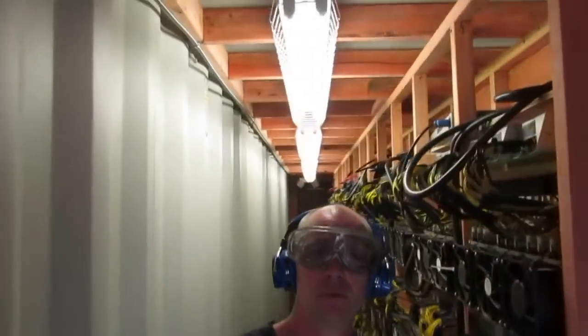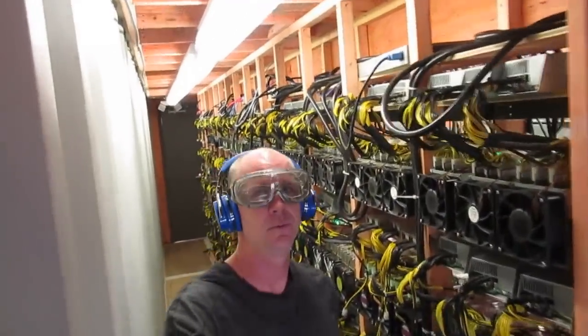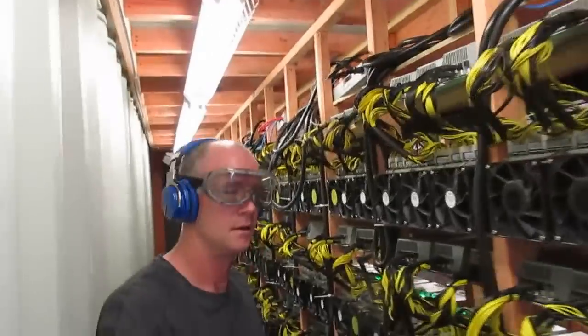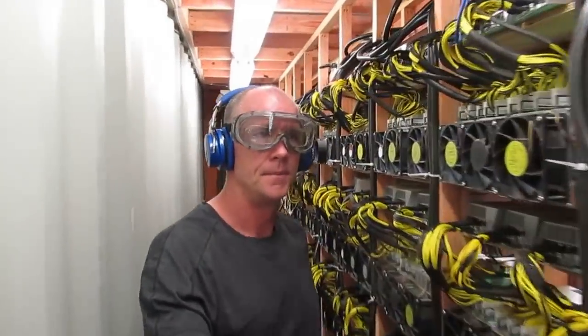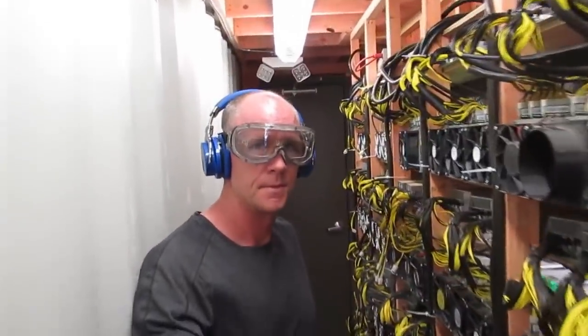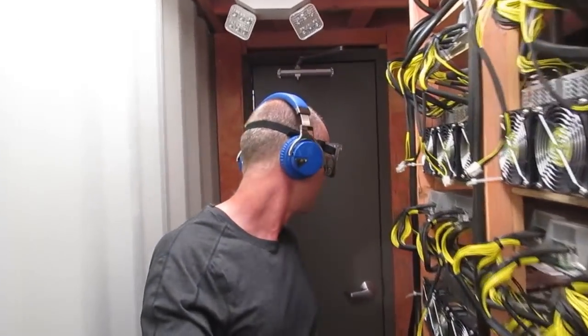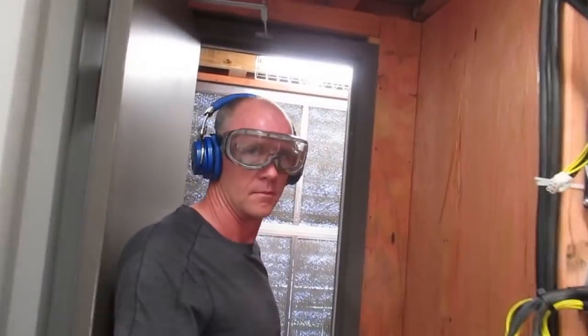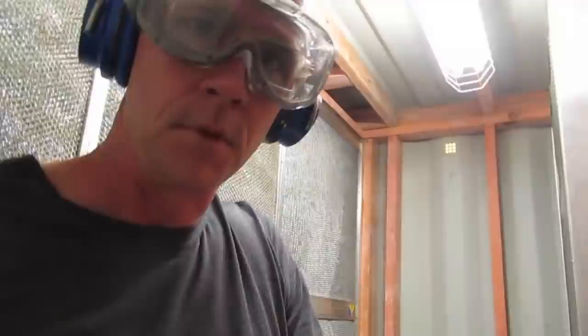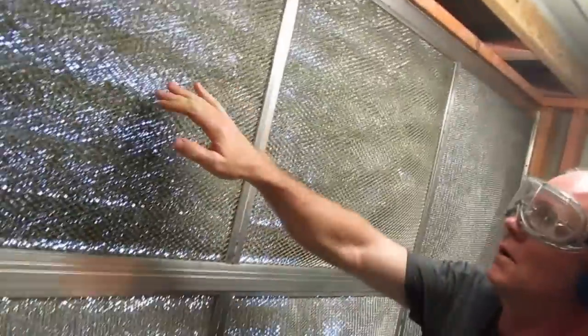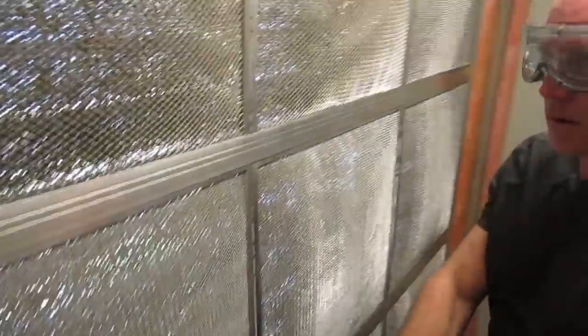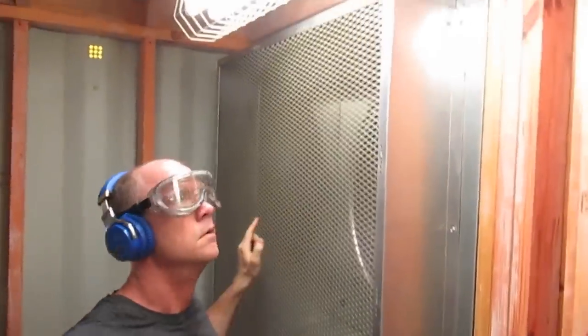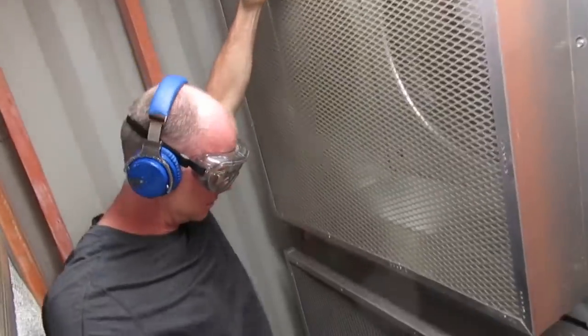This is the hot aisle. It's certainly warmer on this side, and you can see the exhaust of all the miners. This is where we put them in and out of the container. And then in this area here, we've got a door that goes to a mixing area. So we have a vent and filter combination that brings in the 40,000 cubic feet per minute of air. This allows me to change out the filters, and you can see they're pretty much at their limit of air pressure. And here are the two intake fans.